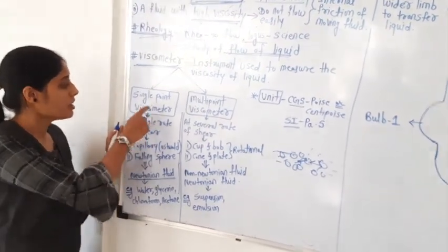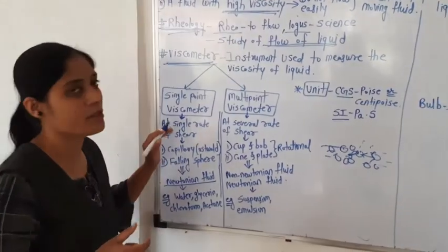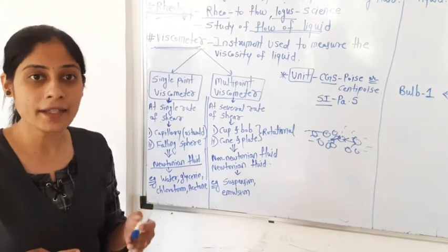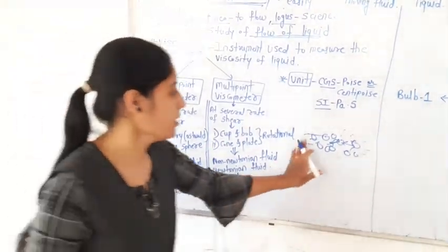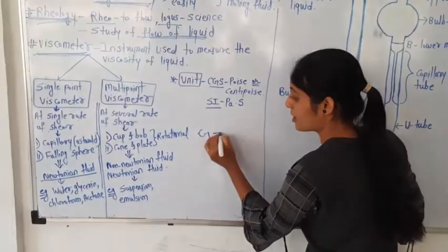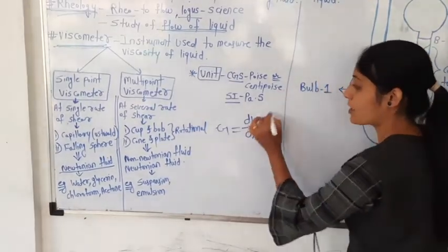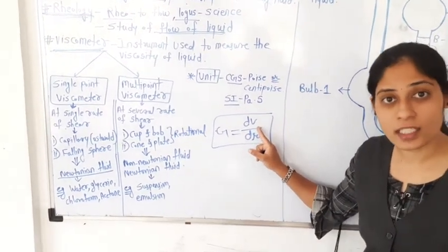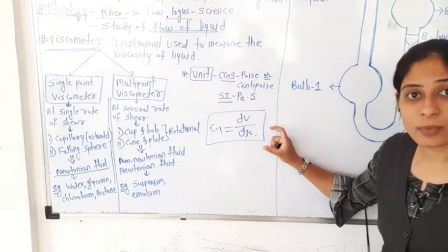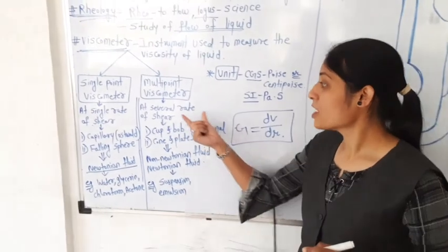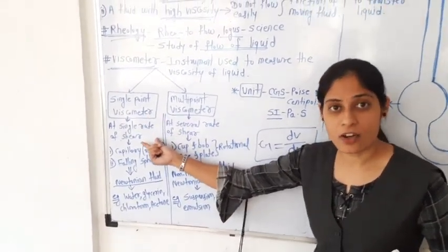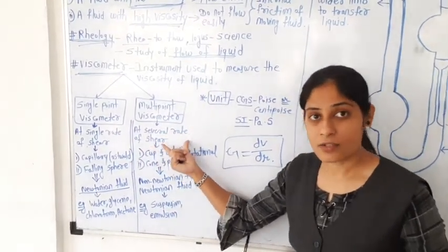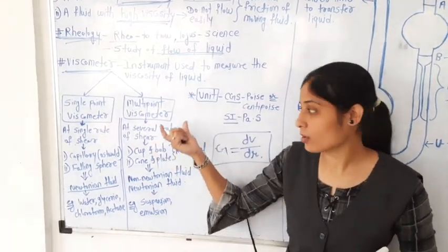The single point viscometer works at a single rate of shear, and the multipoint viscometer works at multiple rates of shear. So what is rate of shear? Rate of shear is denoted as G. G equals dV upon dr — that is, the change in velocity with change in distance. The velocity of the liquid sample changes with change in distance; that is called the rate of shear. The single point viscometer works at a single rate of shear, while multipoint viscometers use multiple rates of shear.